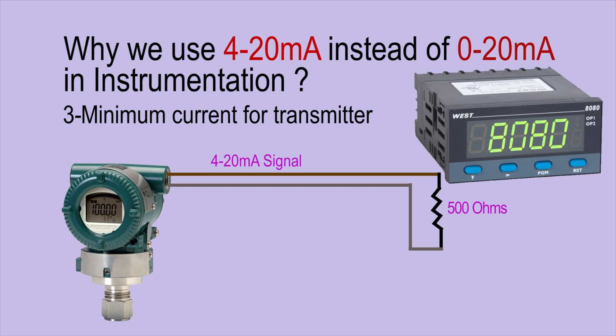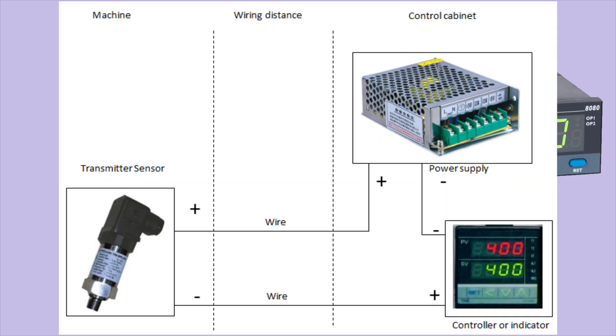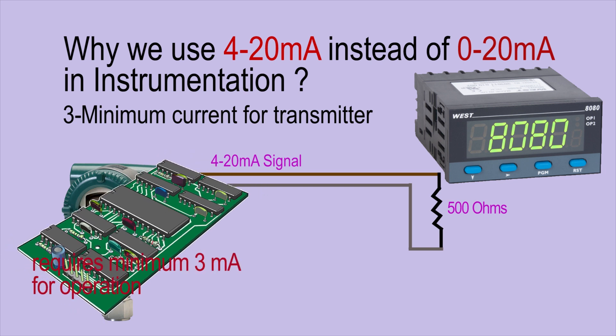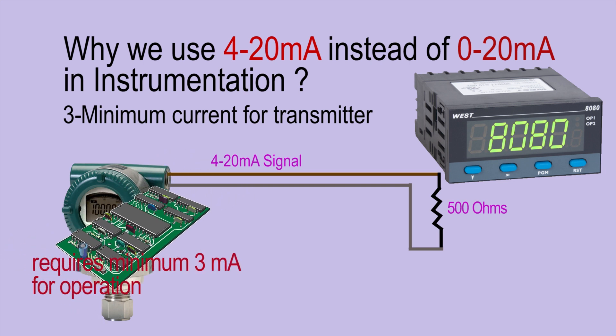Reason number three is the minimum current required for transmitter operation. Most modern transducers use two-wire connections, meaning there is no separate wiring to power the transducer. The transducer's electrical circuit uses the 4 milliamp minimum signal current for its own operation, so this 4 milliamp baseline provides the power needed to run the transducer.